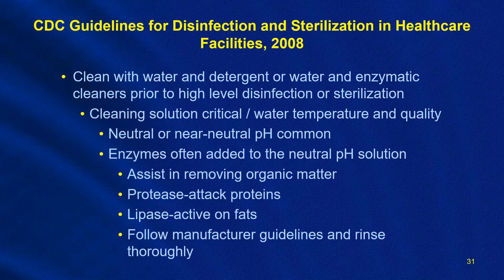Cleaning with water and detergent or water and enzymatic cleaners prior to high-level disinfection or sterilization. The cleaning solution is critical. The water temperatures and quality of the water are critical. You want to use neutral or near neutral pH cleaning materials. Common cleaners contain enzymes and are used to assist in removing organic matter. Protease cleaners attack proteins. Lipase cleaners are active on fats. And you have to follow the manufacturer's guidelines in all of these scenarios and rinse thoroughly with all of these chemicals. It's just mind-boggling the things that they have to know and follow to be compliant with what's recommended by the manufacturer, by CDC guidelines, by recommended practices from AORN and the Central Sterile people, ANSI and AAMI. It makes my mind kind of shiver.